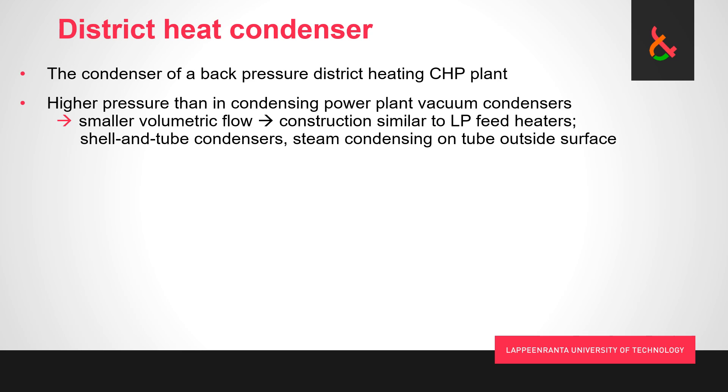These condensers work functionally just like the vacuum condensers of large condensing power plants, but because we're talking about higher pressure steam, we have less volumetric flow rate and can get away with a lot smaller, more compact, simpler construction, very similar to low-pressure feed heaters. These are always shell-and-tube condensers with steam condensing on the tube outside, and practically always U-tube construction.